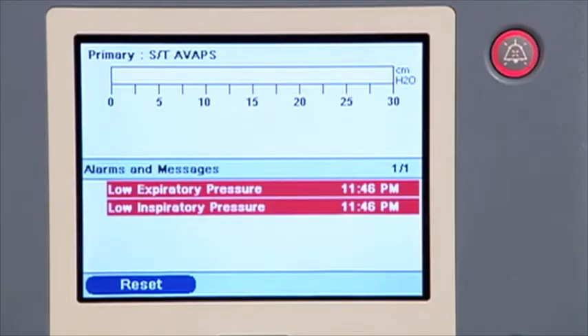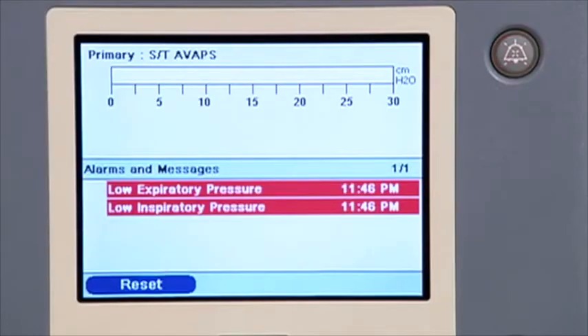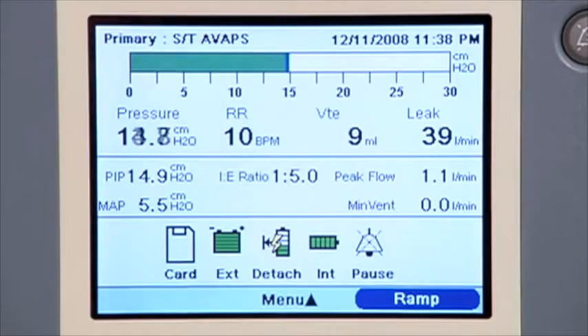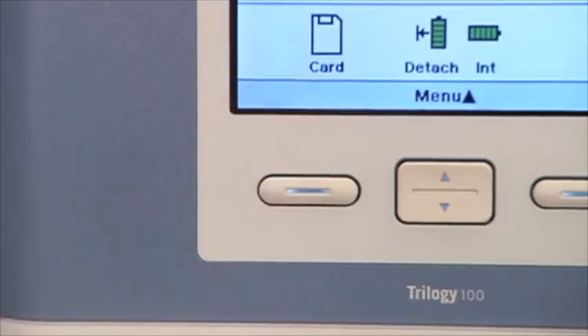The alarms and message screen will show a priority alarm message highlighted in red. You can temporarily silence the audio indicator by pressing the audio pause button. An audio pause message displays in the menu banner on the alarm display screen. The alarm will be silent for a minute, and if the problem is not corrected, sound again. You can press the audio pause button again for another minute of silence as many times as necessary. When audio pause is active and you are on the monitor screen, an audio pause symbol appears. When the problem is corrected, the alarm LED, audible alarm, and the alarm background color will shut off. However, the alarm text remains on the screen until you press the left button to reset the screen.